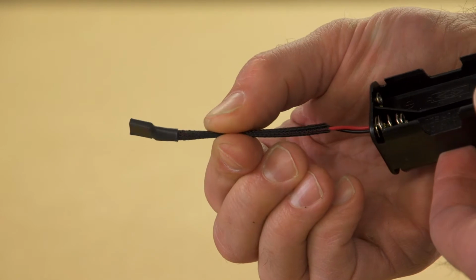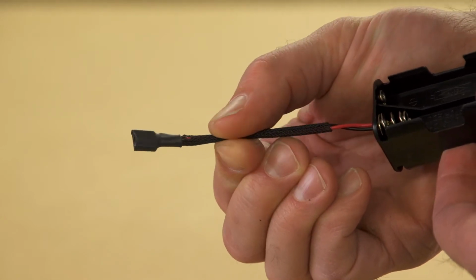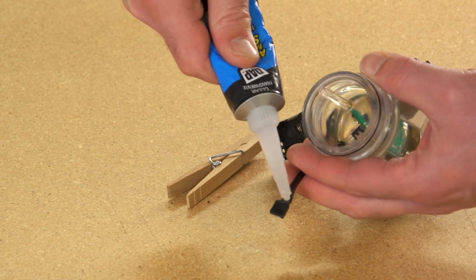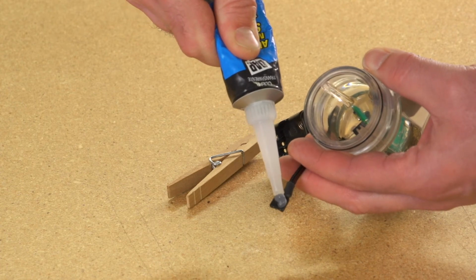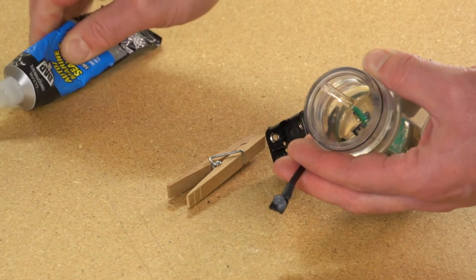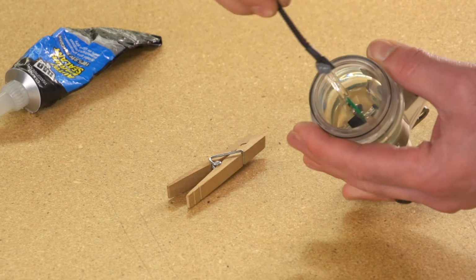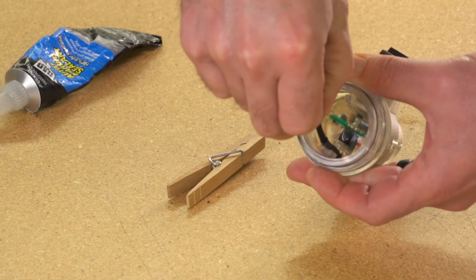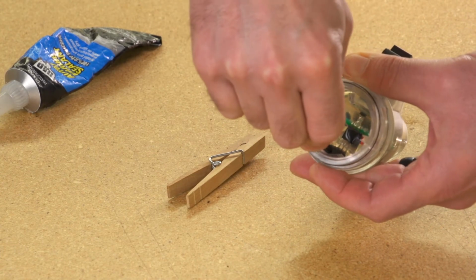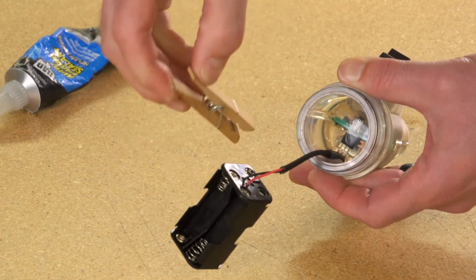Notice on the pack connector that the shrink tubing has been removed from one side. Place a small dab of silicone on the side where the shrink tubing is cut away. Line up the holes in the connector with the 3 pins inside the probe. Center is positive, so as long as the pins are lined up, you can't reverse the polarity.